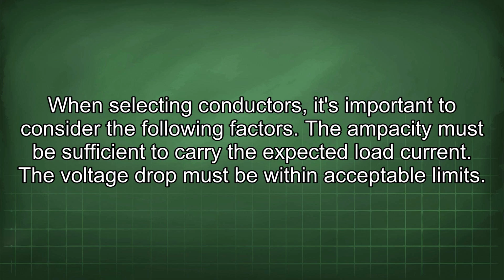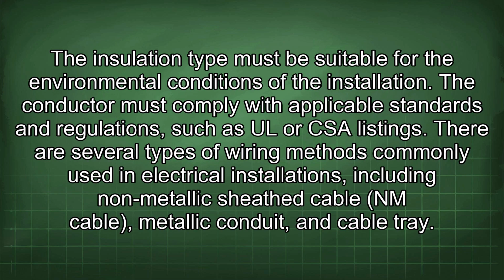When selecting conductors, it's important to consider the following factors. The ampacity must be sufficient to carry the expected load current. The voltage drop must be within acceptable limits. The insulation type must be suitable for the environmental conditions of the installation. The conductor must comply with applicable standards and regulations such as UL or CSA listings.